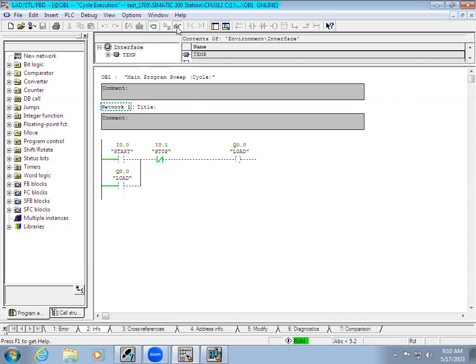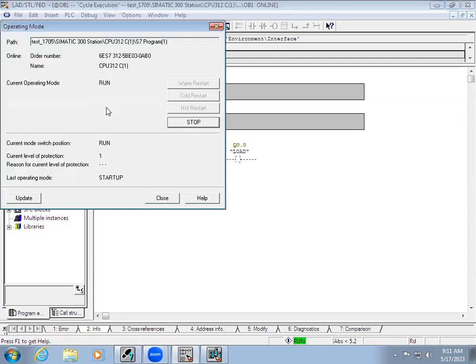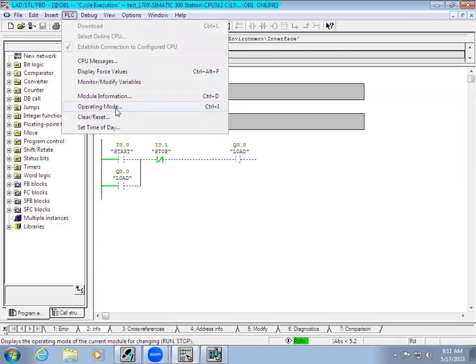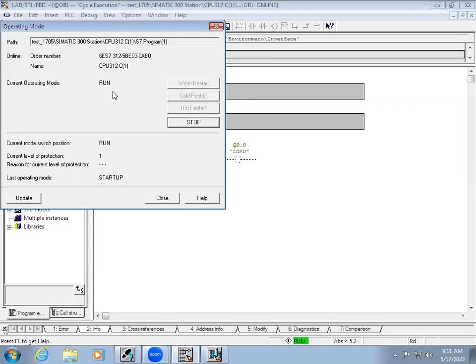Now in your controller, if you turn on the input it will get activated. If the controller is in Stop mode, it will not download. What you can do is go to Operating Mode — it will show the current operating mode. If it is in Stop, you can give Warm Start so that your controller comes back online, then download and change it to Run mode.